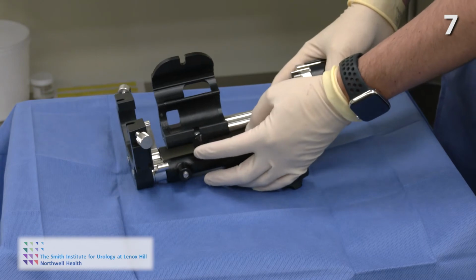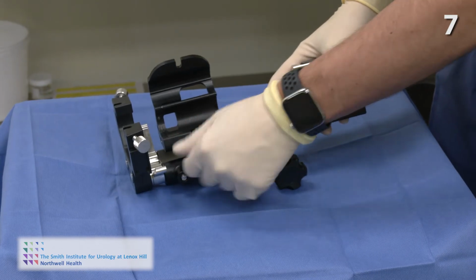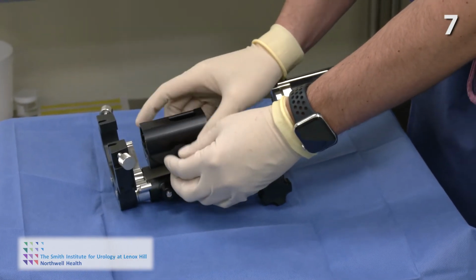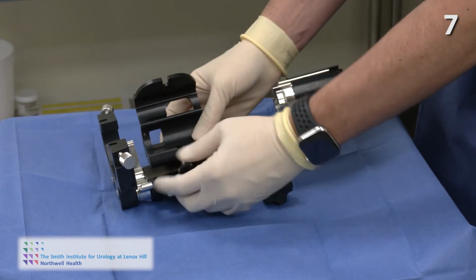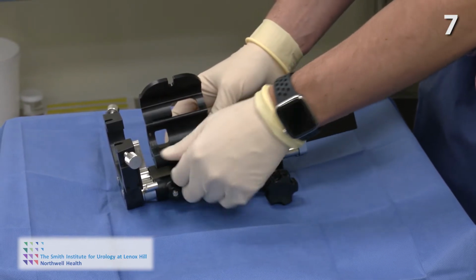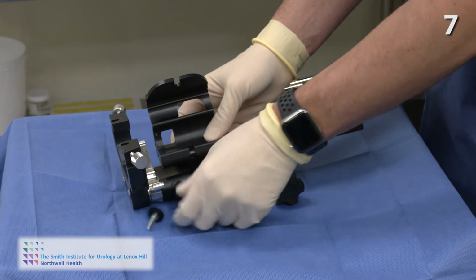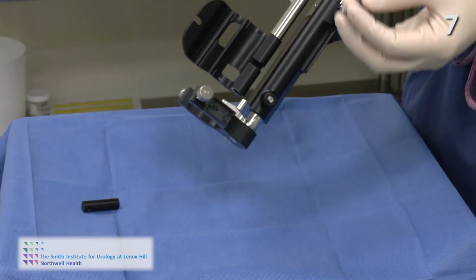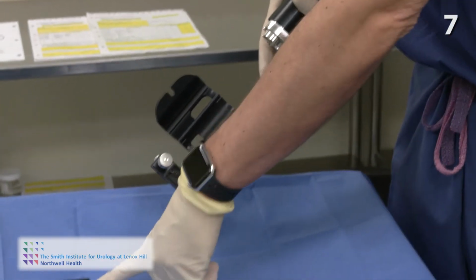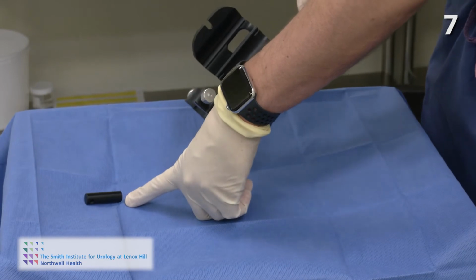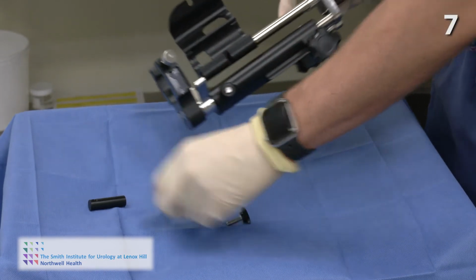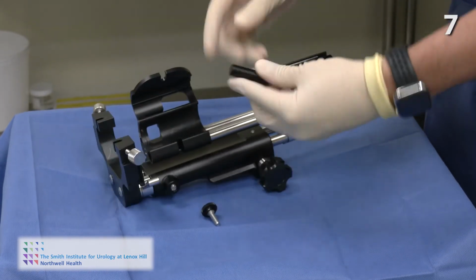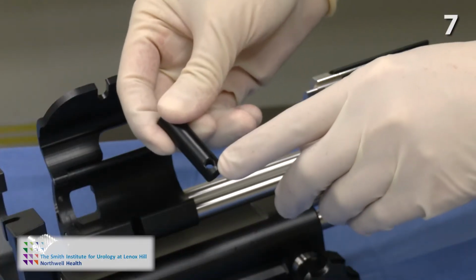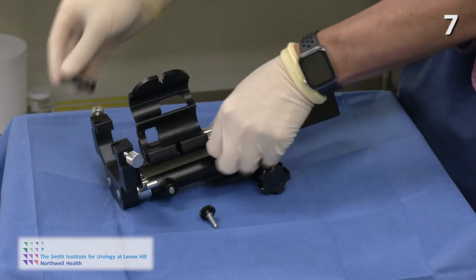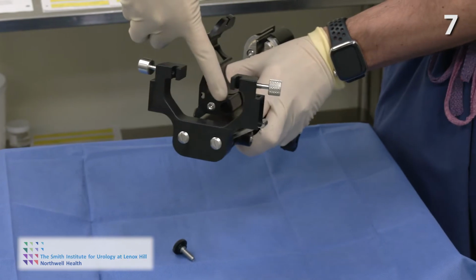The other thing that's really important, if you look here, there's a black screw. This gets lost because it's used to loosen to remove the ultrasound probe. I'm going to undo it and show you what happens. Most people don't realize they'll have the screw, but they're not paying attention to look what happened. The black piece falls out and no one ever sees this again. The way to put this back is pretty simple. There's the opening for the screw. We slide it in the front. There's an opening right here in the hole.